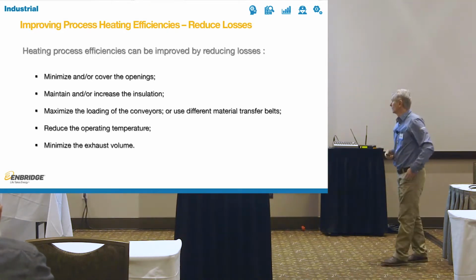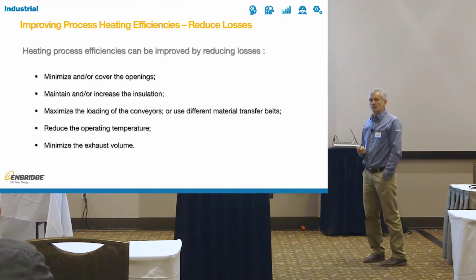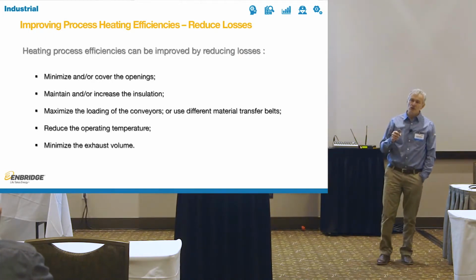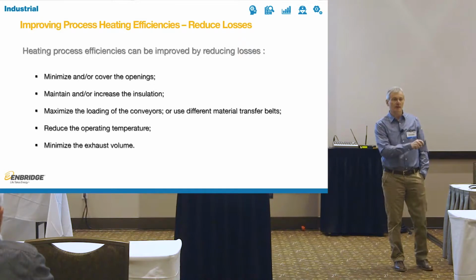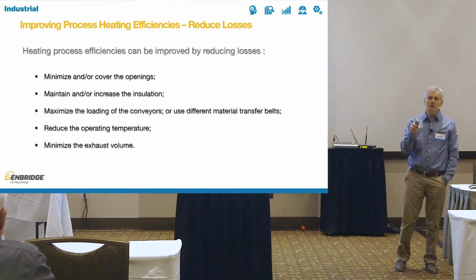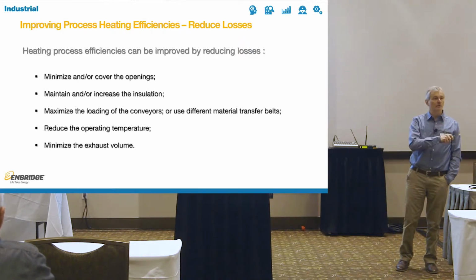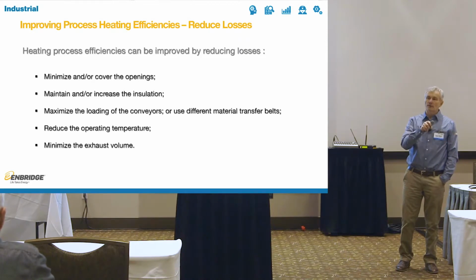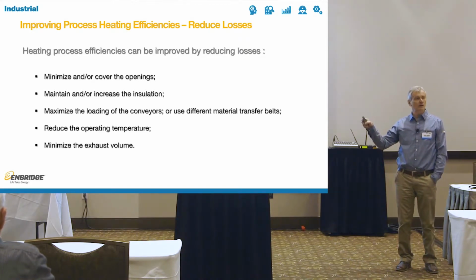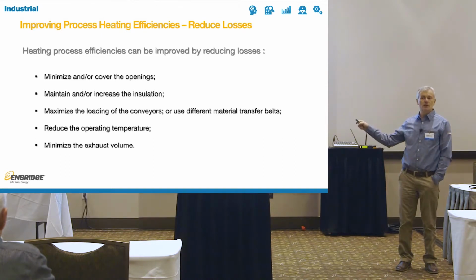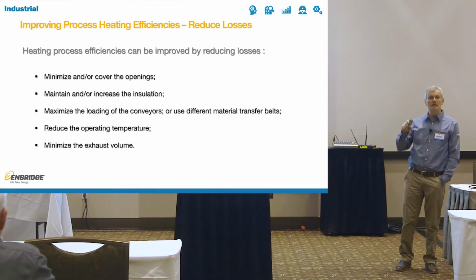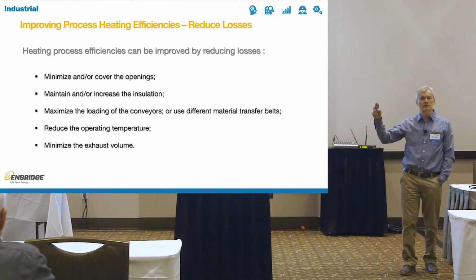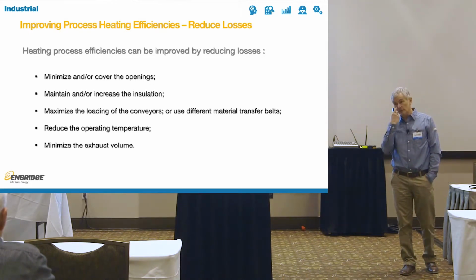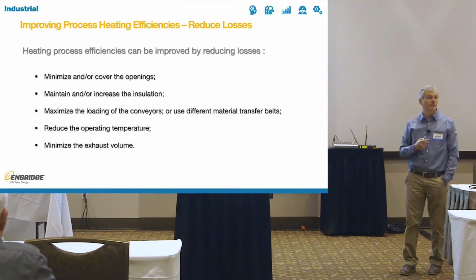Fix that first. Maximize the loading of the conveyors. Many, many finishing lines will have conveyors that carry the parts. Those conveyors, believe it or not, will take more energy than your part itself. So if you have 1 hook loaded for every 20 hooks unloaded, that's where lots of your energy goes. You're just heating that chain that goes around your facility. Yes, it heats your facility, but not in the most efficient way.